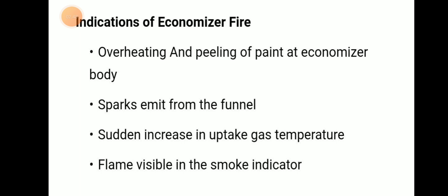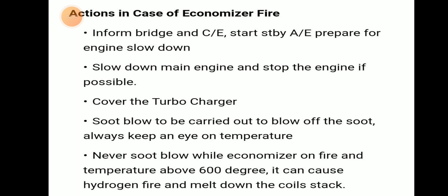To summarize the indications: overheating and peeling of paint at the economizer body, sparks emitting from the funnel, sudden increase in uptake gas temperature, and flame visible in the smoke indicator. When economizer fire occurs, we need to inform the bridge and chief engineer, start the standby auxiliary generator, and prepare for engine slowdown.